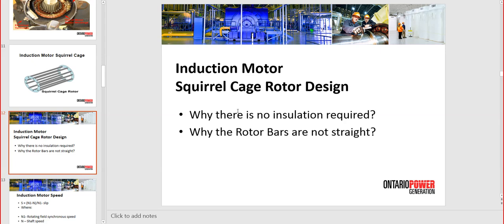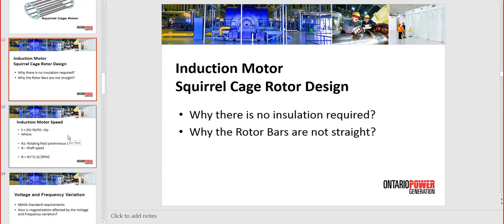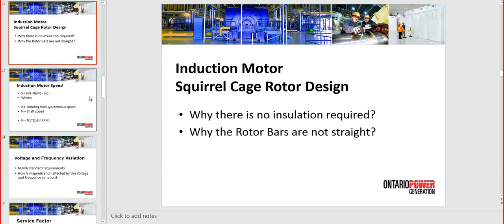Okay, induction motor squirrel cage design. We said already no insulation is required because the voltage is very low, and the actual copper and aluminum are very good conductors compared to iron, but there are some little leakage currents that we take care of with those Baldor-invented copper rings on both sides to protect the bearings. If you don't do that, the bearings will have a much shorter life.